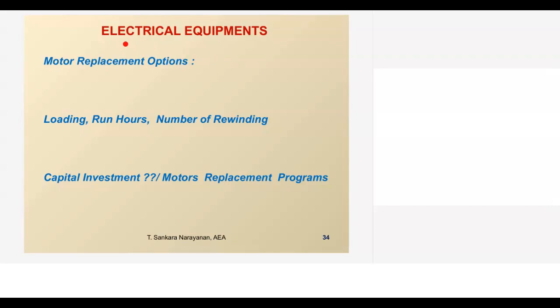So for electrical equipment, in some places motor replacement options can be considered. The motor replacement option is a function of loading, running hours, and sometimes the number of rewindings, because the same motor is operated for 15 years. If we have done 2 or 3 rewindings, definitely that will also result in certain additional loss. So that is why the existing losses are all taken. There are certain evaluations on how to identify motors for replacement. One is based on the loading, run hours, number of rewindings, and years of efficiency level. For each parameter you can give a value. Then, based on the higher weightage, motors can be replaced.